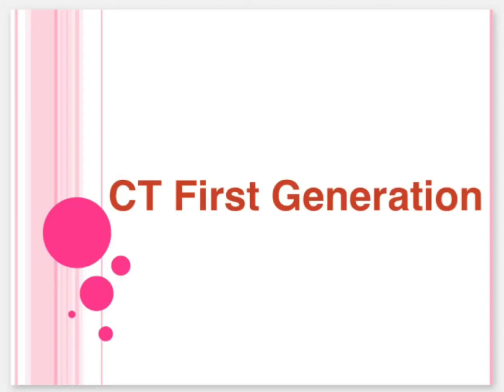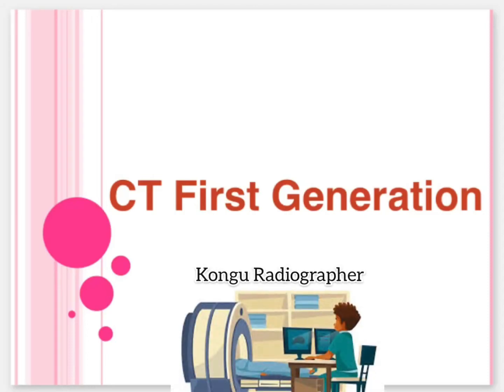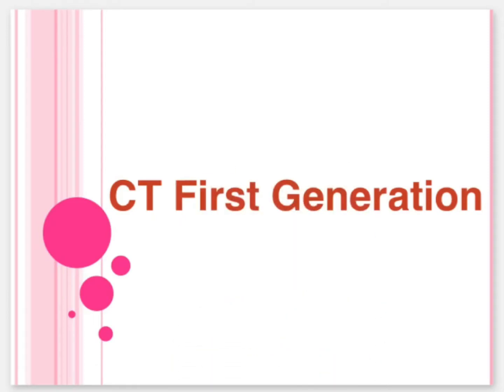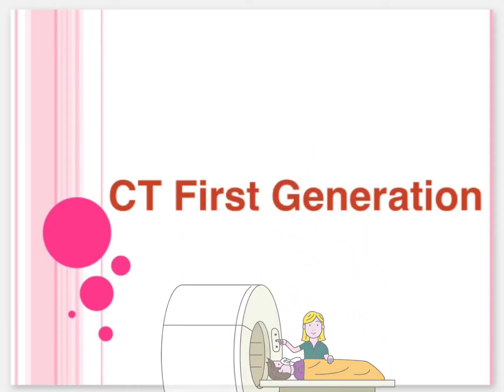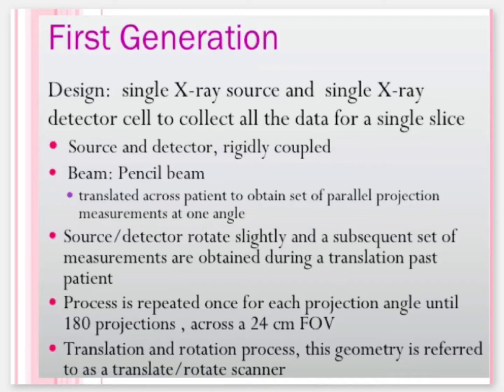Hey friends, welcome to Kongu Radiographer channel. Today's topic is about CT First Generation. First Generation Design: Single X-Ray Source and Single X-Ray Detector. To collect all the data for a single slice, one source and detector are rigidly coupled.